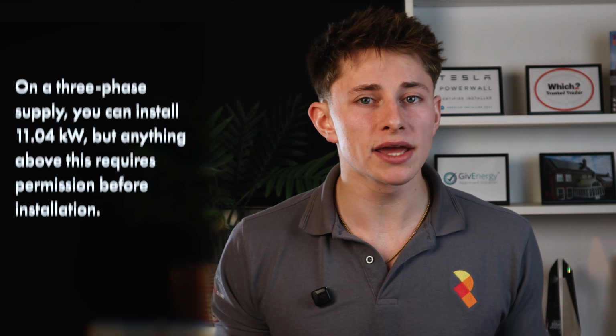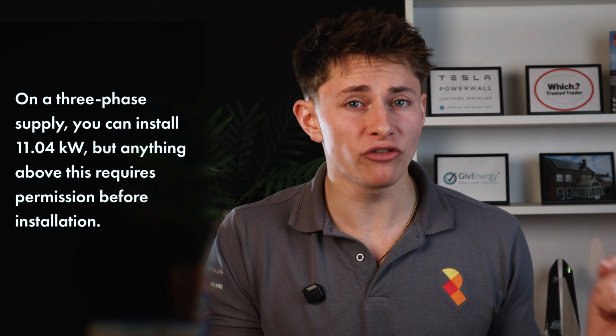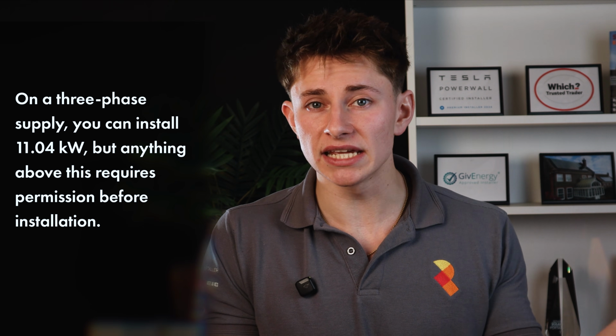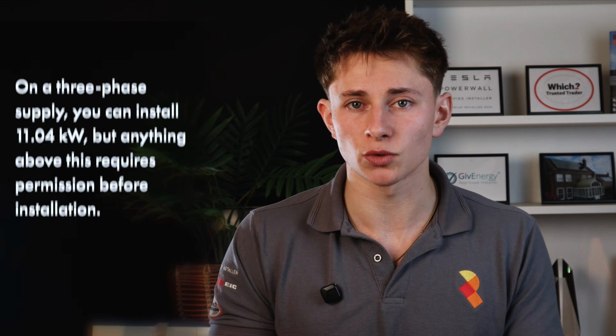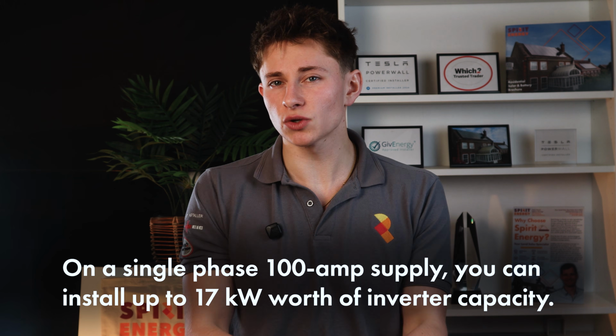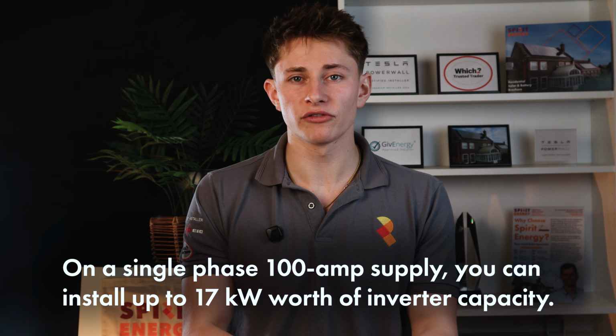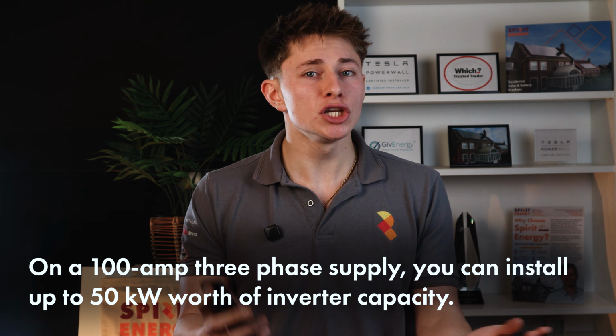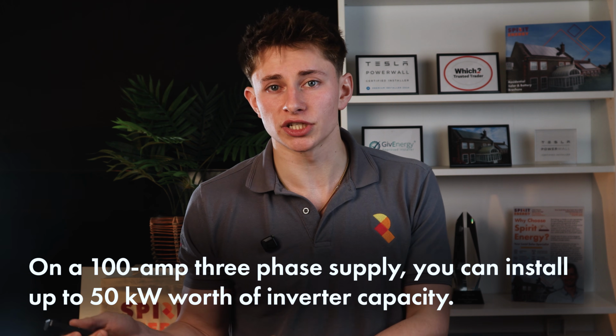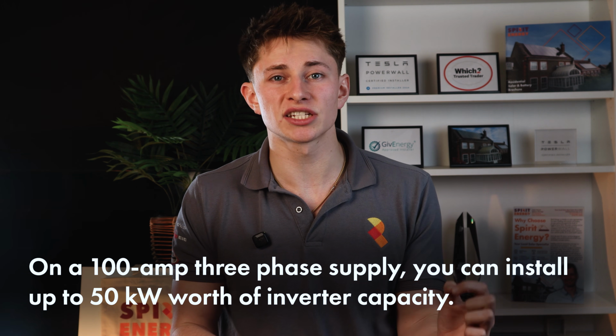On a 3-phase supply, you can install 11.04 kilowatts, but anything beyond this requires permission before you install. On a single phase 100 amp supply, you can install up to 17 kilowatts worth of inverter capacity. On a 100 amp 3-phase supply, you could probably get away with up to 50 kilowatts, but beyond 50 kilowatts, you need a special type of DNO application, which is far more complicated.